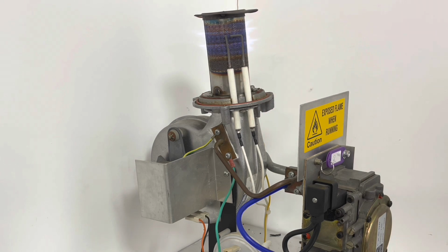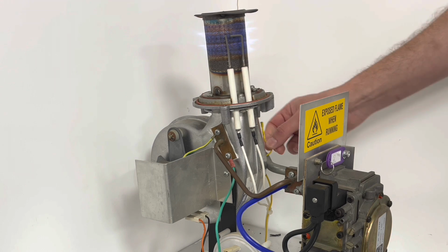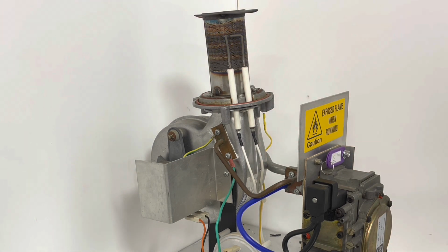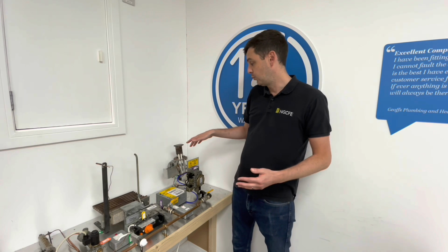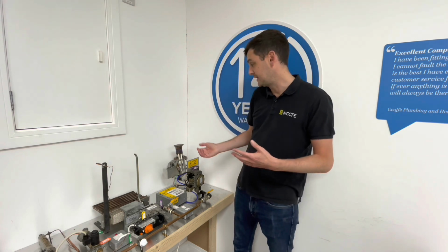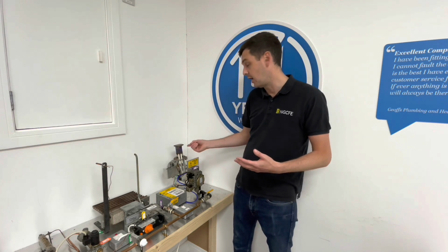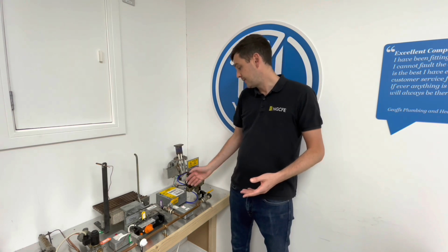So in the same vein, if I was to disconnect the probe on the rectification probe, I've taken that current away from the board. Now there's no way of the current getting back to the board. So when the burner lights, the board doesn't receive DC current. So what will happen is it'll light, but it'll still carry on trying to arc and ignite because the board doesn't know there's a flame there. So then it'll go through that sequence a number of times and then eventually go to lockout.